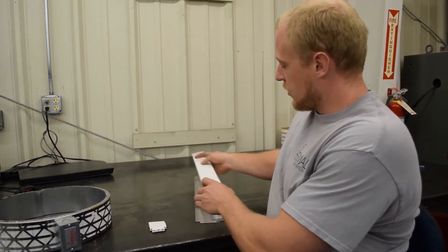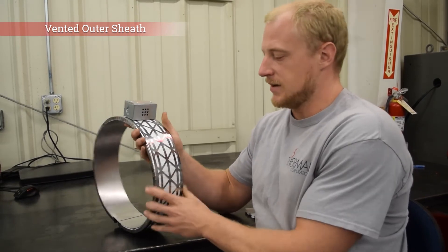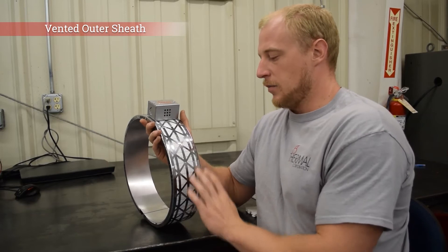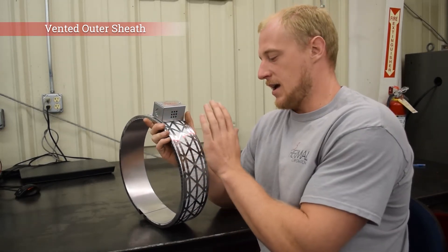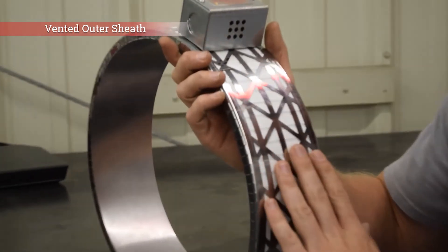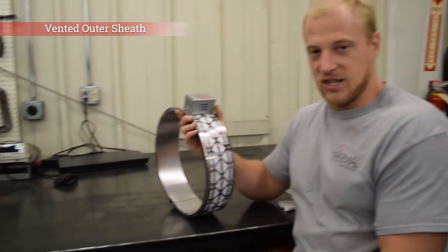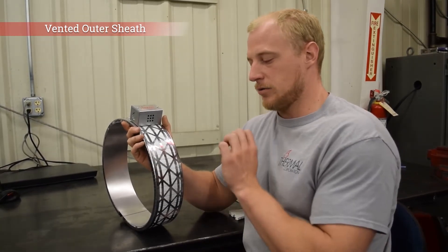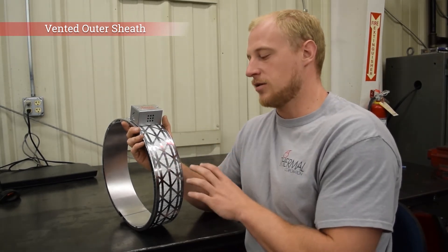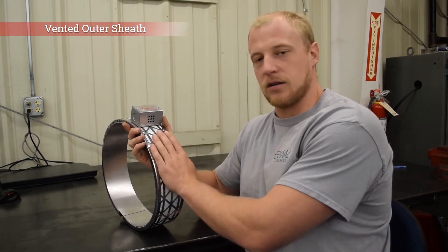We also offer a third option that we call a vented ceramic band heater. That contains the same ceramic knuckles with the same resistance element wire wound through it, but then it has no ceramic paper insulation. The stainless steel outer sheath has triangular holes cut in it, so it's not solid. The reason for these triangles is that it retains its structural rigidity, but it also allows airflow to get to the knuckles and to the resistance wire to cool it off. So if you have an application that requires a heater band that can also be air cooled with a fan, then this is a good option for you.